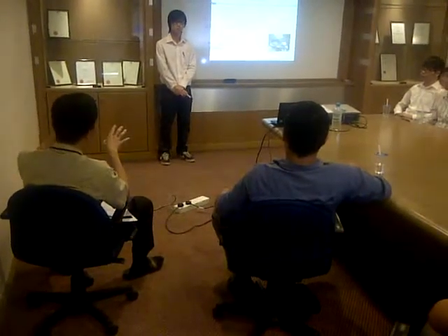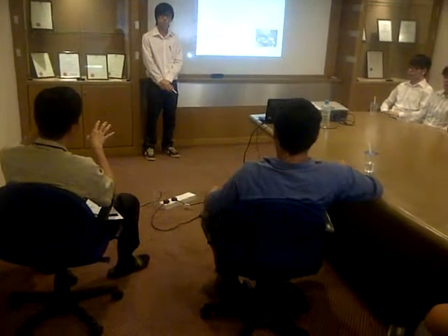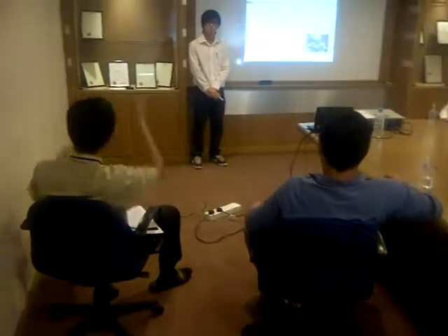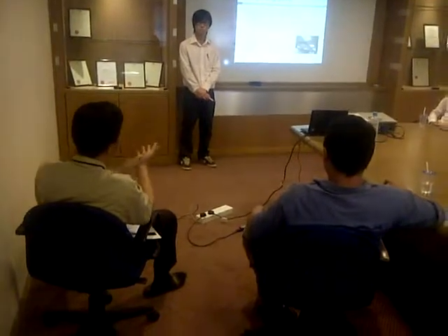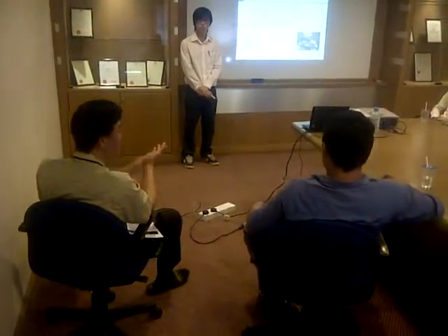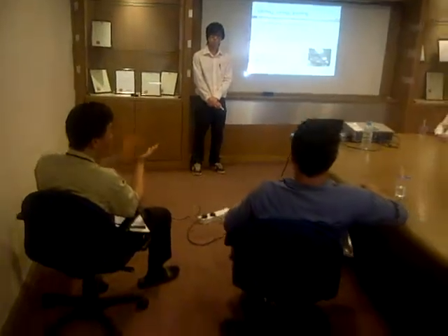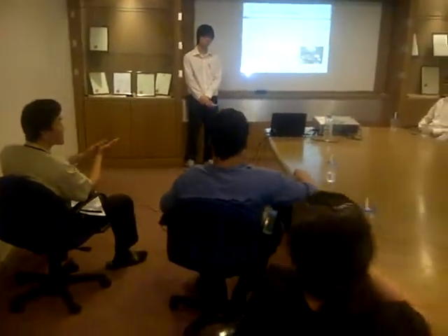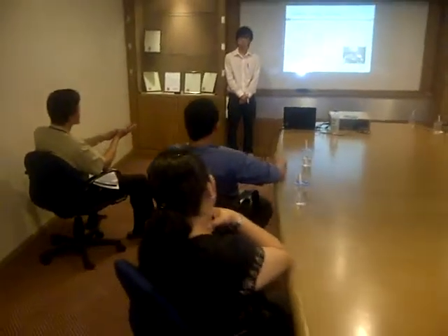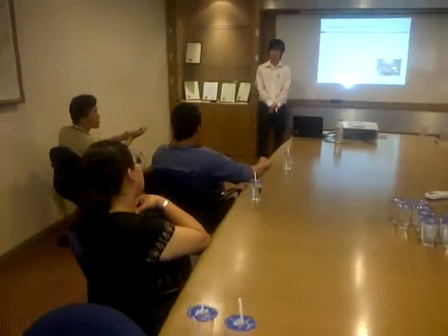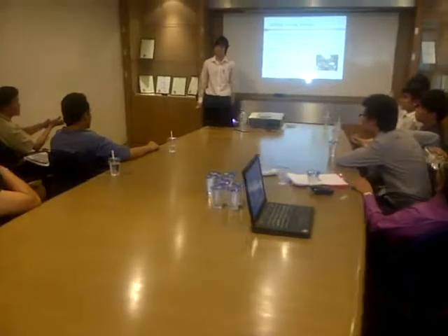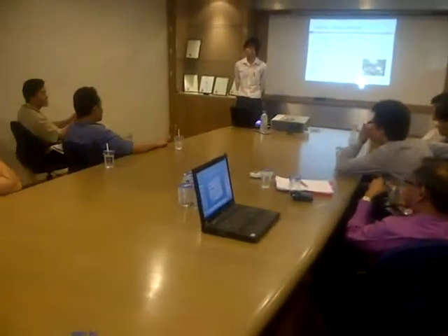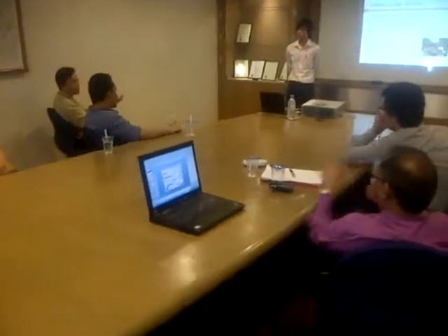When you compare with fluorescent, in fact, the only heat really dissipated is not really the lamp, it's only at the ballast. So when you touch the ballast, even with your hand, you don't feel that hot. Even though it's a little bit warm, you don't feel it will actually hurt you. The heat is maybe around 40-something degrees Celsius or even 50, but it's not that hot to be fair. But for LED light, the heat sink, when you touch it, you feel heat.